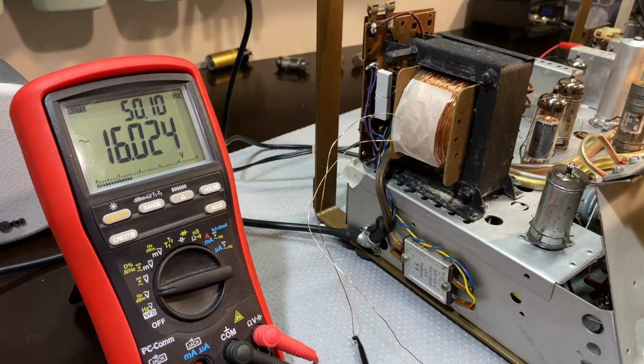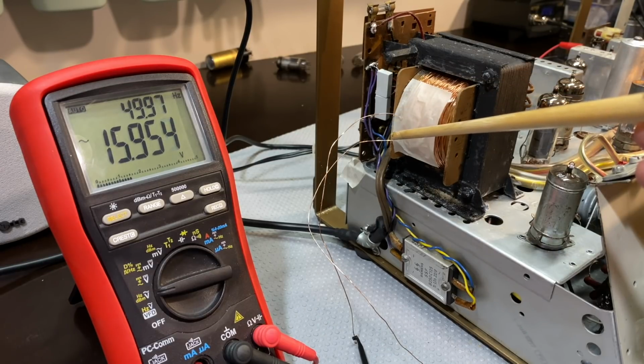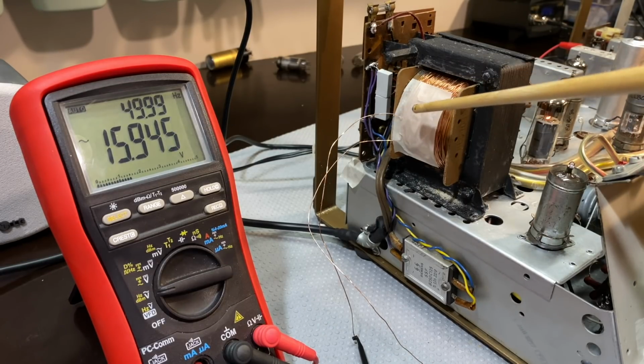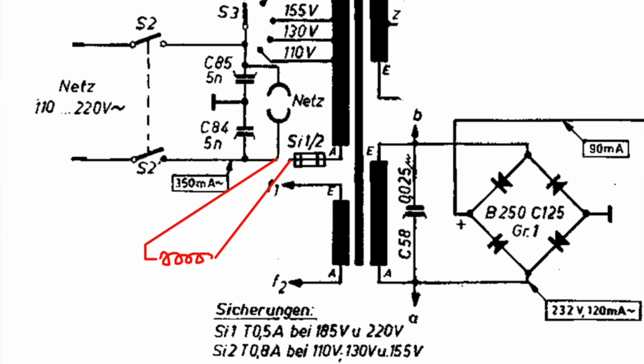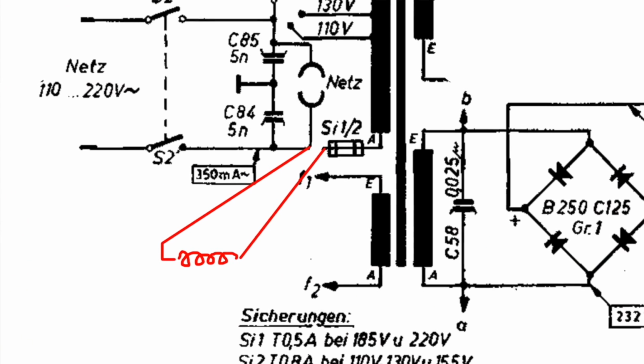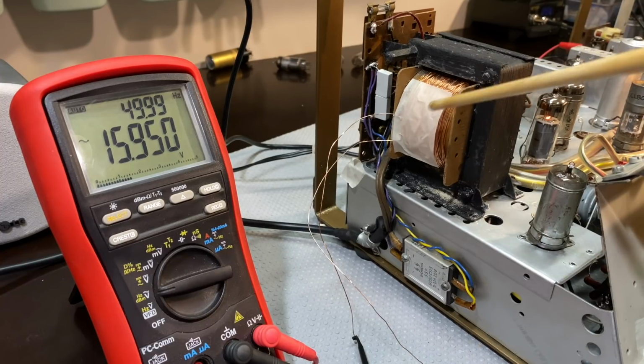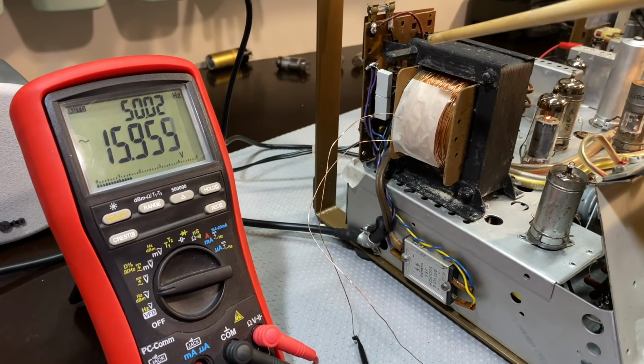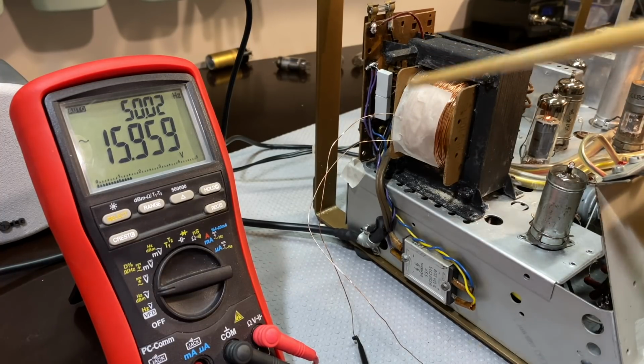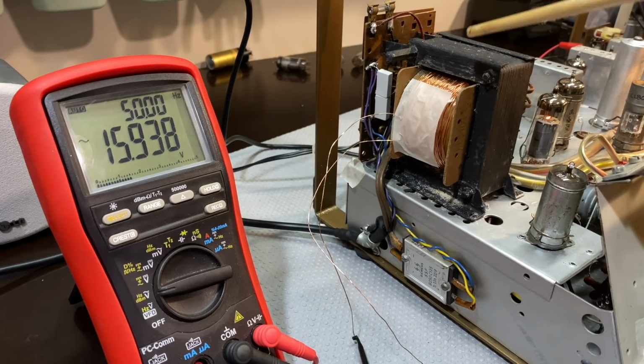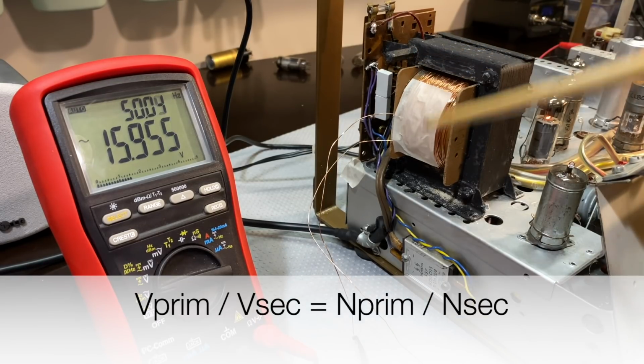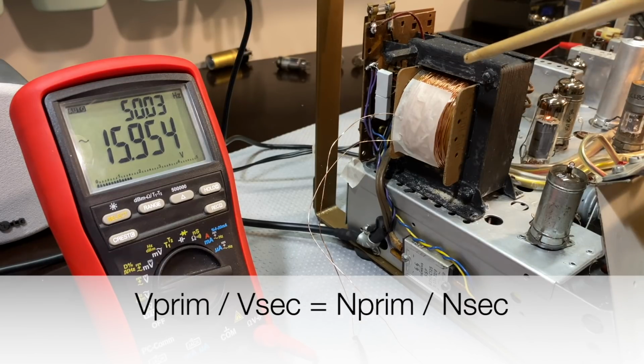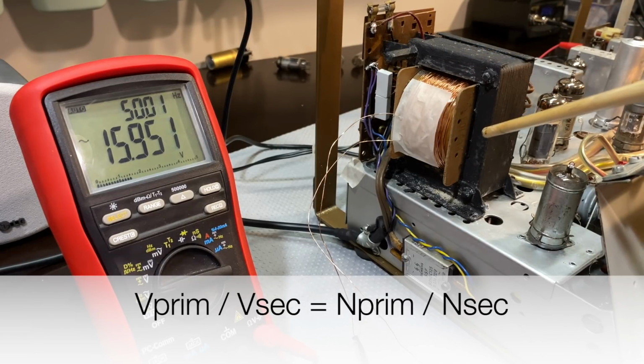Now, how can I use that to control the voltage this thing is giving me? Well, what I can do is literally put that coil, that winding, in series with the original primary. Now what will that give me? If you know a little transformer theory, you know the ratio of the voltages equals the ratio of the turns. So the primary voltage divided by the secondary voltage equals the primary number of turns divided by the secondary number of turns, okay?